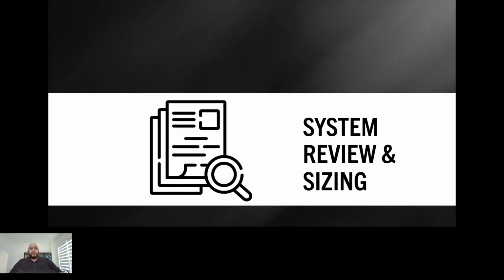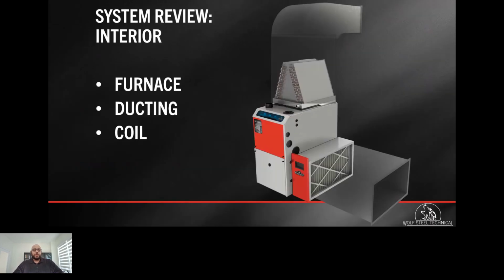So I wanted to talk about reviewing a system and sizing it. To review the system interior, we're going to be looking at the furnace, the duct, and the coil. What type of furnace is being used? Oil, gas, electric? Is the upgrade necessary? Are they taking advantage of any of the rebate programs, and what are the conditions to qualify? You already want to utilize the equipment that's already there. So ensure the coil is suitable for the furnace and the heat pump, as well as whether the ductwork can handle the CFM and the capacity of the unit.